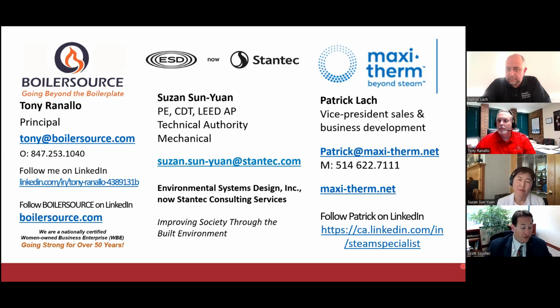Tony, we had an engineering-oriented question. When using a vertical flooded heat exchanger in conjunction with a low temperature hydronic building heating loop or other type of low temperature system, when something like that makes sense, is there still a boiler efficiency advantage if the condensate returns is above 130 Fahrenheit?